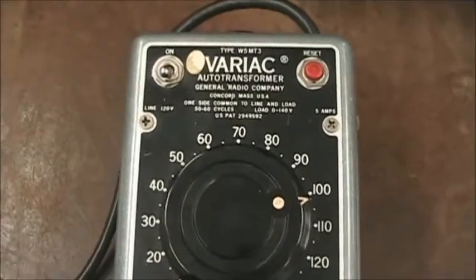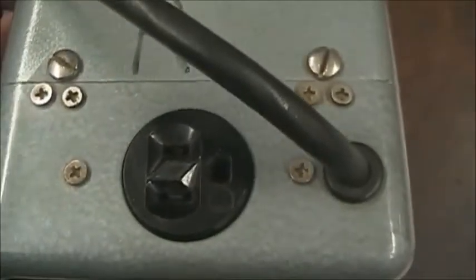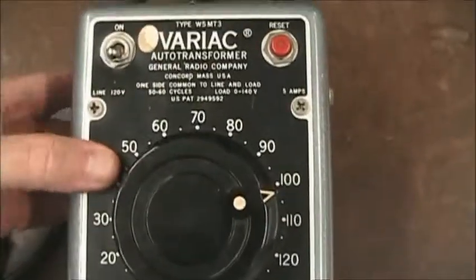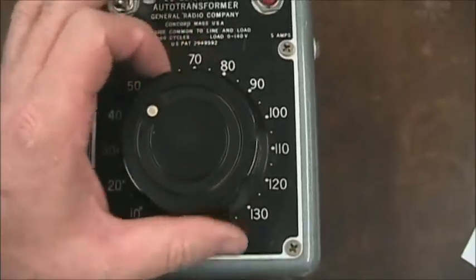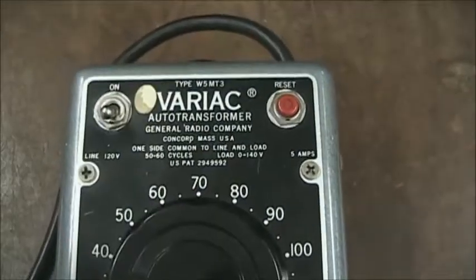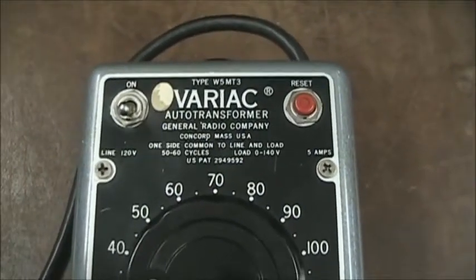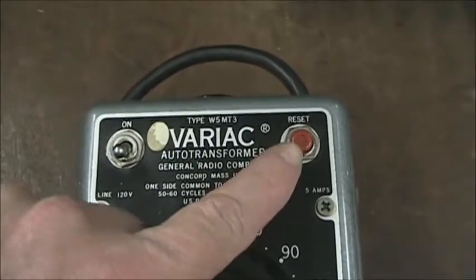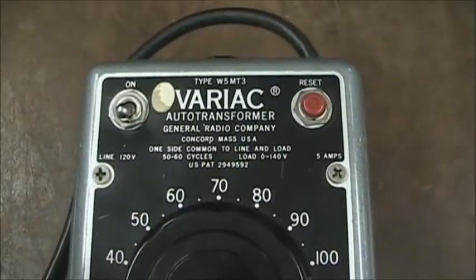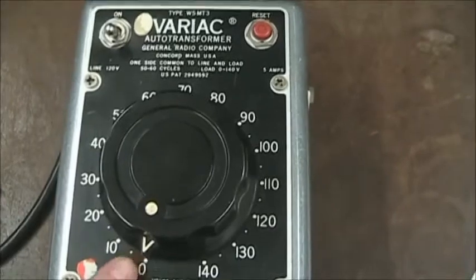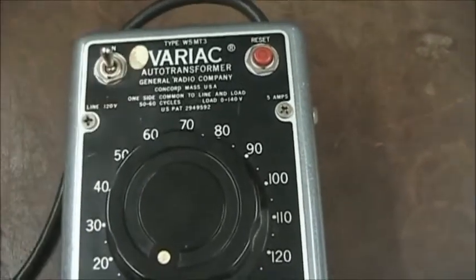The first element is a variac. A variac is a special form of transformer that is adjustable to allow us to adjust the source voltage. The variac has an input power cord, an output power outlet, and it also has an on-off control, a variable voltage control, and a circuit breaker. When we use the variac, we normally have the voltage set to zero before we energize the variac.